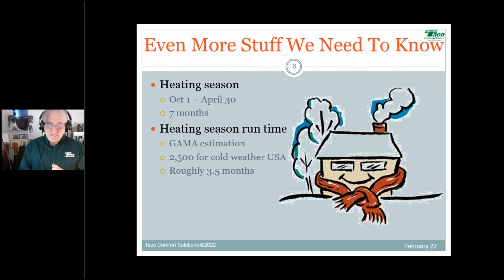Also, heating season runtime. This comes from the Gas Appliance Manufacturers Association, and for the cold weather parts of the US and Canada, we're looking at about 2,500 hours. Some areas get up into 3,000 hours - that's how many hours over the course of the heating season the equipment is actually on. Interestingly, if we identify the heating season as October 1st to April 30th, there are parts of the West Coast, like Northern California into Oregon, where the runtime is estimated at 3,000 to 3,500 hours, even though it doesn't get that cold. So the heat load says it doesn't get that cold, but the amount of time it has to run is a bit longer than here in New Hampshire, which is about 2,000 to 2,500 hours.